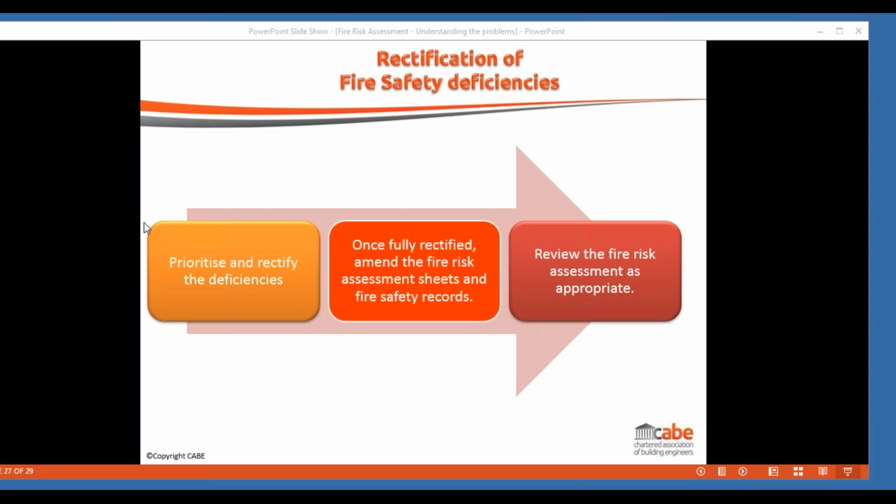If you look at something like retail, if it's outside shop hours and we've got people in warehouse or back of house in stock rooms, it's not only important about the level of awareness and whether they know whether something's going on in unoccupied areas, but it's also what sort of level of training of those people had. A lot of workplaces will do regular training of their staff, will do practice evacuations, and all the sort of things that in terms of a record of what's going on you'd expect to see when you do the risk assessment. But do they actually train the cleaners who only turn up at the premises in the middle of the evening or first thing in the morning?